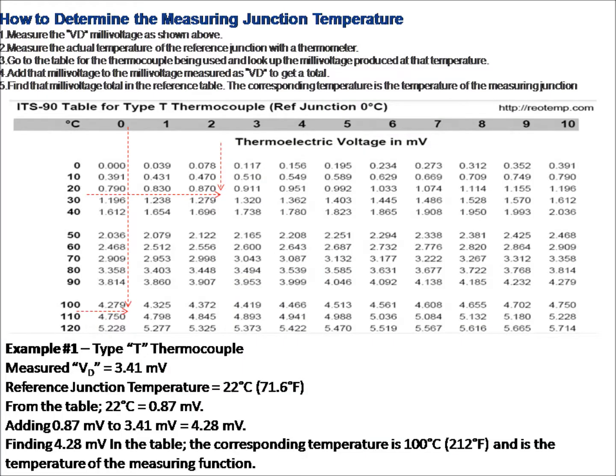To determine the measuring junction temperature: first, measure the millivolt at the thermocouple head — for example, 3.41 mV. Then measure the reference junction temperature — for example, 22°C — and find the corresponding millivolt from the chart, which is 0.87 mV. Add the two millivolt values: 3.41 + 0.87 = 4.28 mV. Now find the corresponding temperature from the chart, which is 100 degrees Celsius.